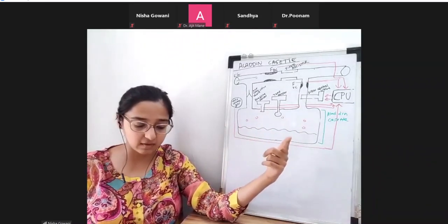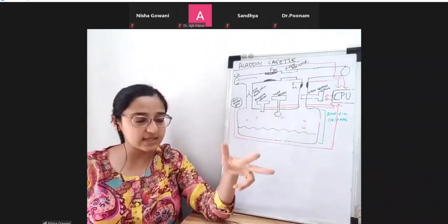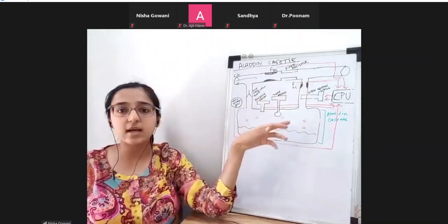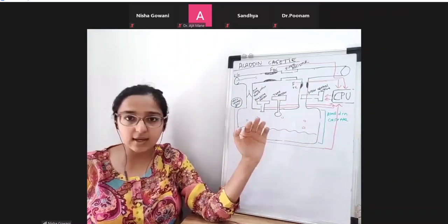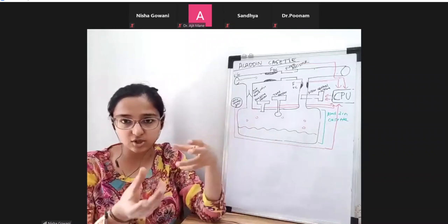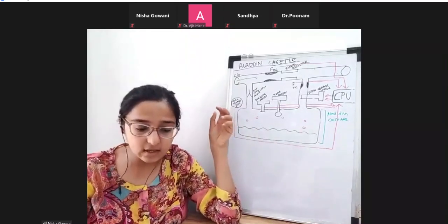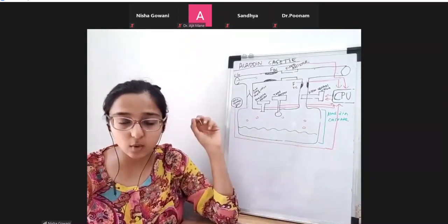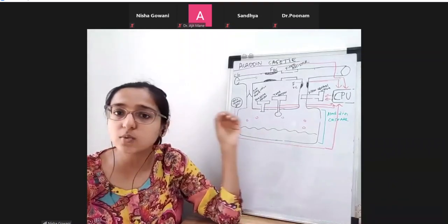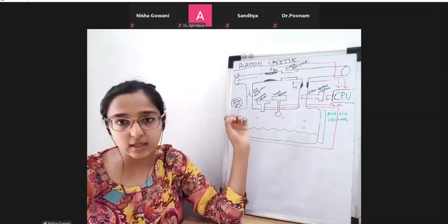Then when you remove the cassette, you might be worried that the fresh gas will leak out. It will not leak out. There are valves which prevent the leakage of the fresh gas when you are changing the cassettes. It's also protected from overfilling and tipping. Overfilling and tipping are two problems which were there in the variable bypass vaporizer, but those problems don't exist over here.